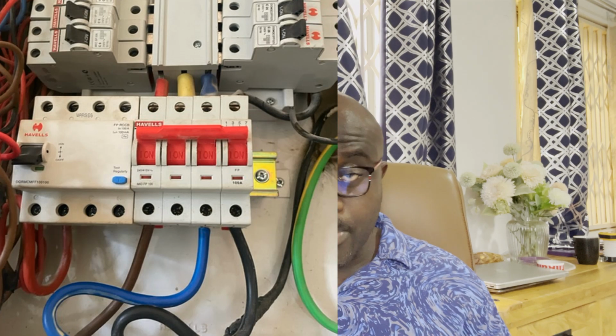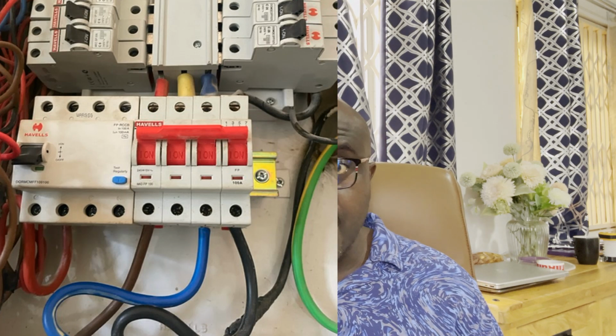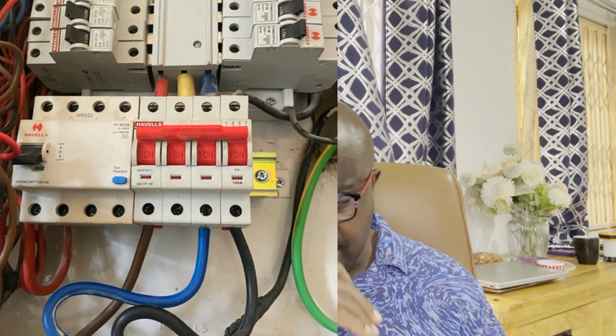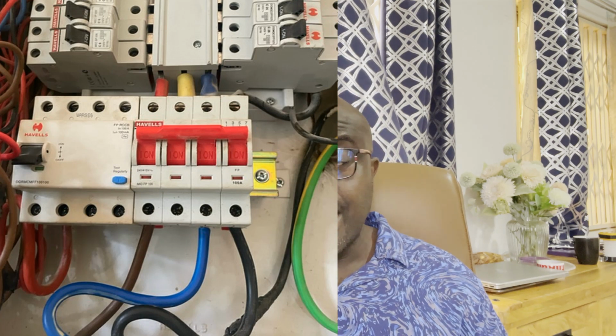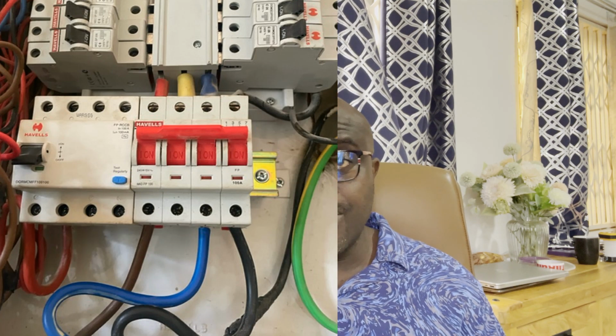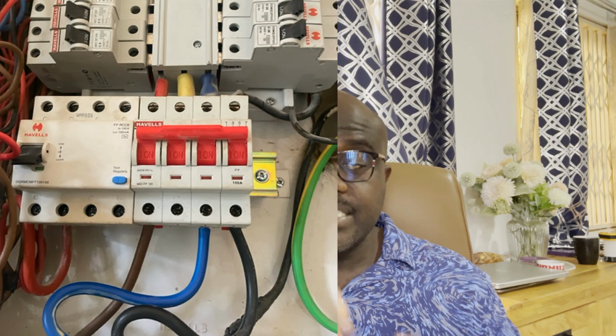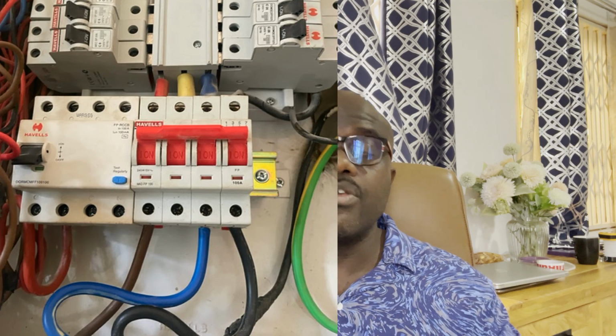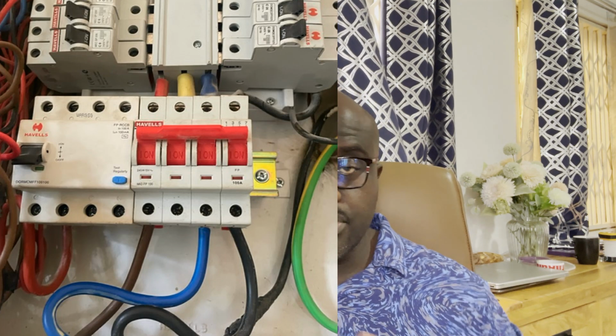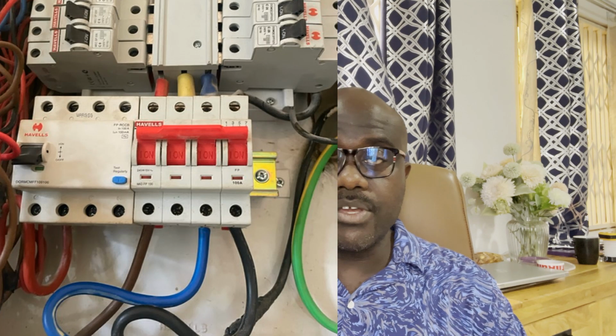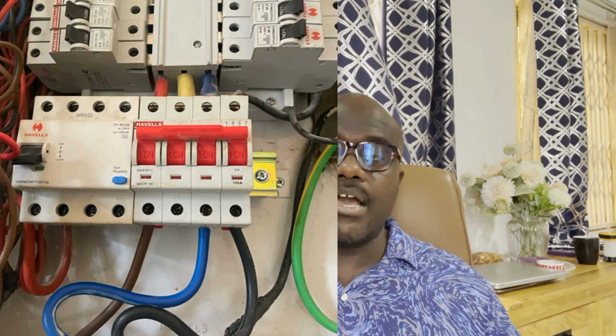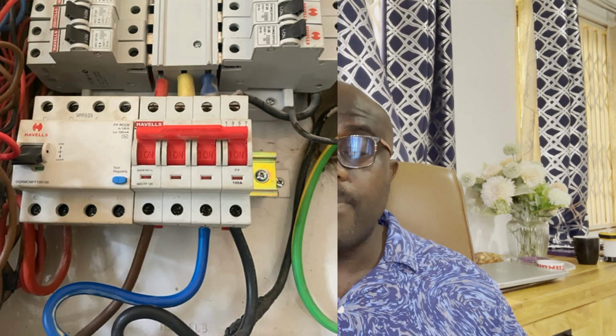Another cowboy thing, very dangerous thing, is the earth cable. Now, earth cables are always the green and yellow cables. Okay, these are standard, industry standard green yellow. When you turn up to a distribution board and electrical installation, wherever it is, and you see a green yellow cable, you know, that's my earth cable. But for some reason, this electrician had used the earth cable to wire as a live conductor, as one of the phases. Why? Why would you ever do that?